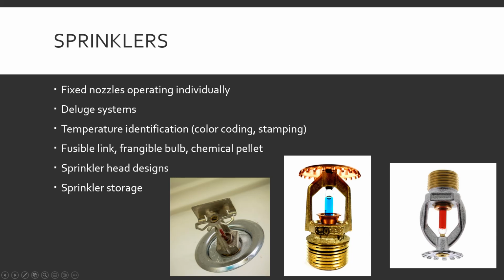And up here we have an upright sprinkler head, and you can see the little teeth are pointed down. Think of this kind of like an umbrella. Water comes up, hits this, and gets deflected out the sides and back down. So these sprinkler heads are set up on top of the pipe. These ones here, these are pendant sprinklers. These are the ones that are hanging down from the water pipes. These are the ones that get hit with the ladder or the forklift or what have you and set off the system. And you can see by this shield how it's more of a flat kind of disc, shooting the water out and breaking up the pattern.